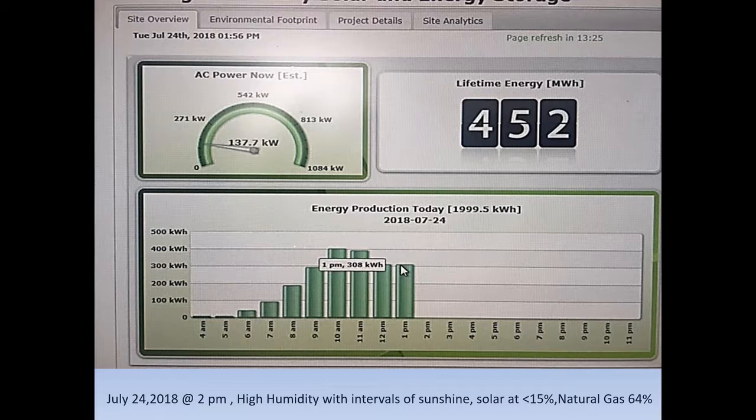This slide I show quite a bit — it shows our dependence on solar on a particular day. It was a little overcast but hot and humid day, and the humidity really brought these numbers down. It's a one megawatt system but it was only putting out 137 to 138 kilowatts. Relying on solar during these periods, especially in the late afternoon when overcast is thick and clouds are coming in, is where the batteries are critical. We're charging them in the morning when the sun's bright and clear, getting the batteries filled, and then using them during the afternoon when solar output drops.